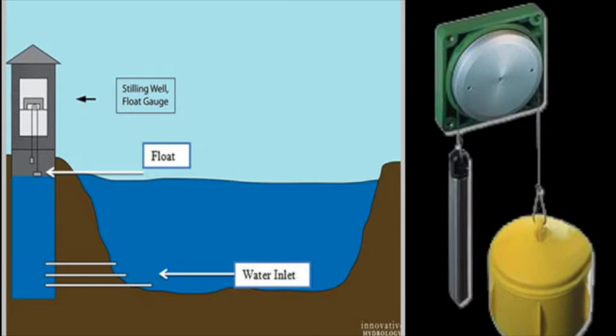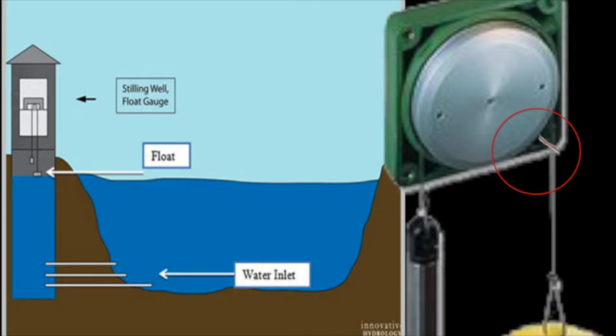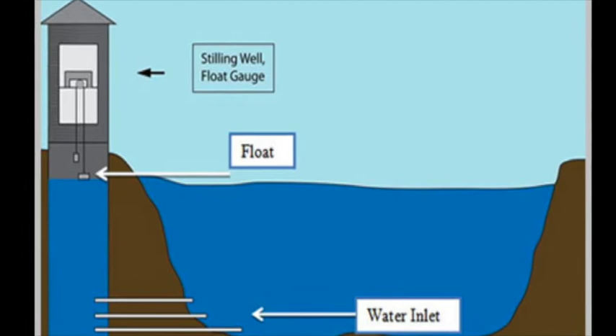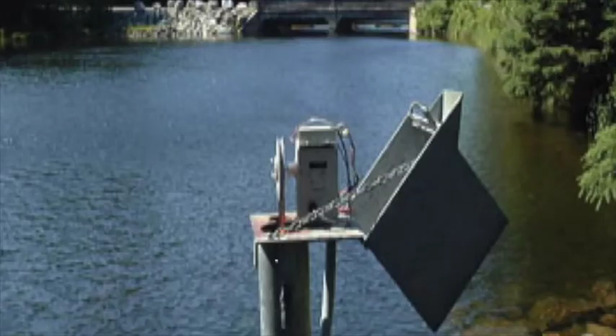As we can see, the installation is generally on a bridge, or a special structure is built. The stilling well is connected to water by pipes, so we should ensure the inlet pipes are not choked by debris. We also check the tape and pulley system; the tape might be torn and displaced from the pulley. Another thing that can happen is some obstruction, like a wooden stick, preventing the float from touching the water. All these conditions can give wrong readings.